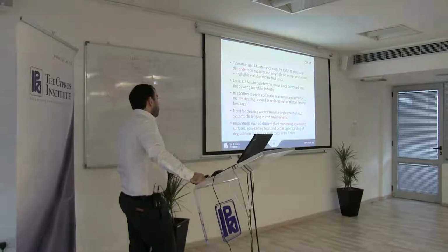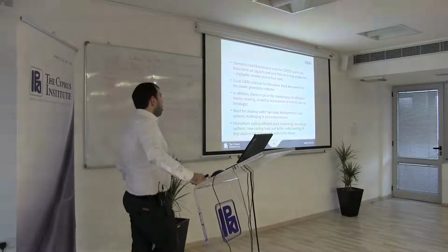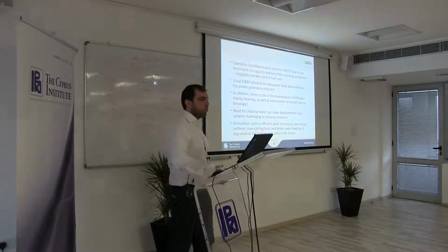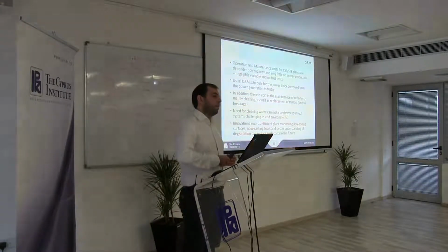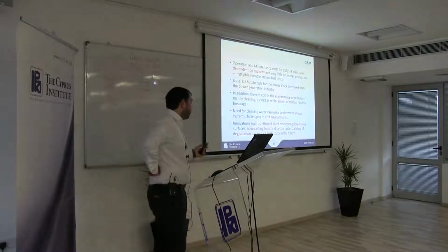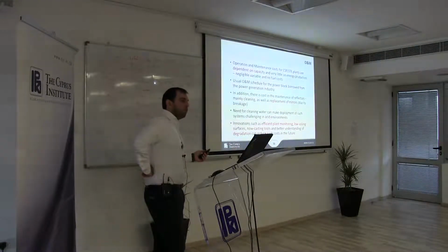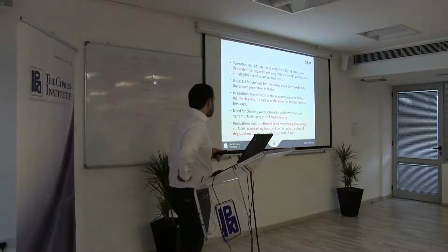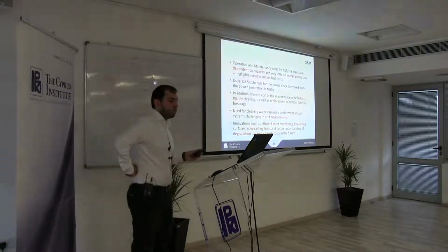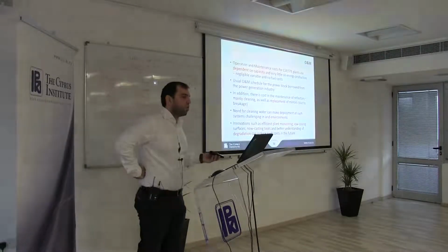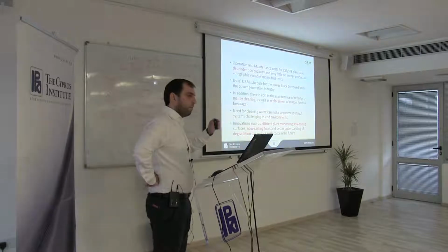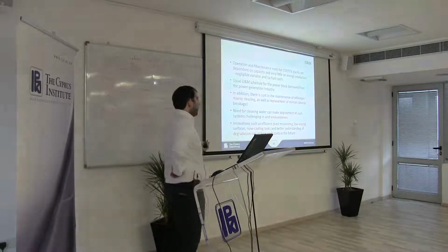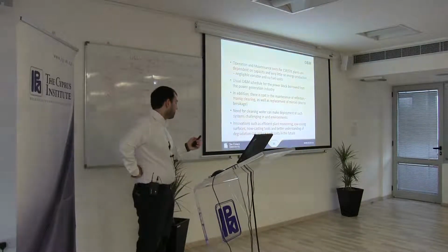While we might have quite high costs in case these plants are deployed in arid environments, and we need water for cleaning of the mirrors. So in case there is an environment with very low access to water, it might be challenging to clean the mirrors, so it adds an extra cost to the system. But innovations such as efficient plant monitoring, low soiling surfaces, so avoiding dust or particles from settling on the mirrors, and better understanding of degradation can reduce these operation and maintenance costs.